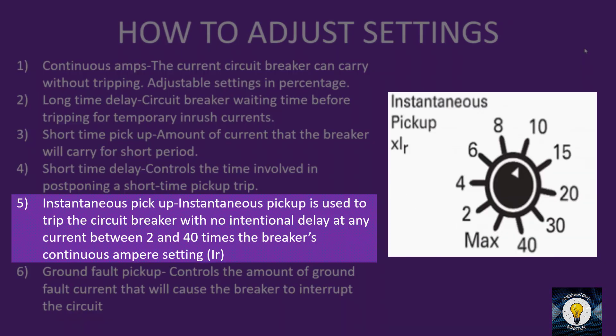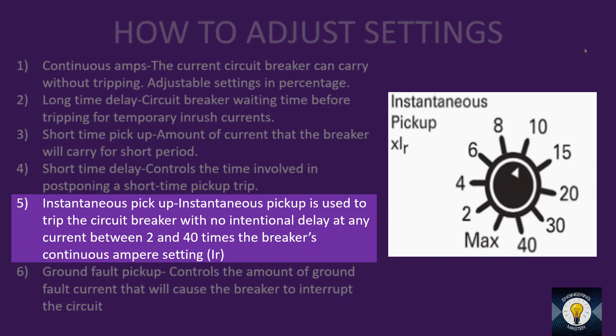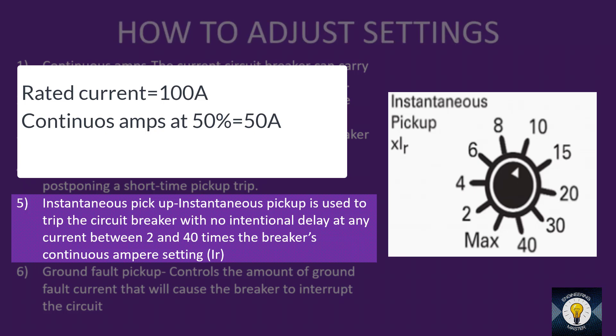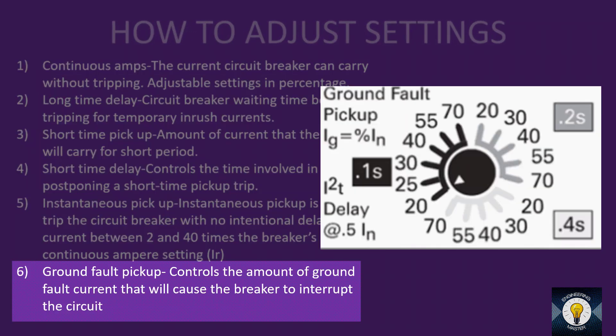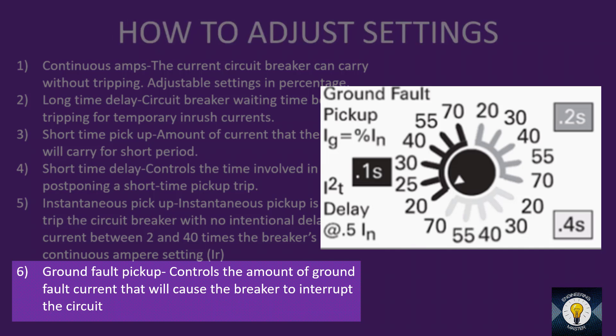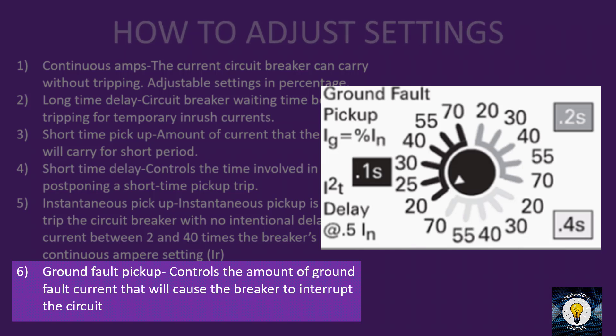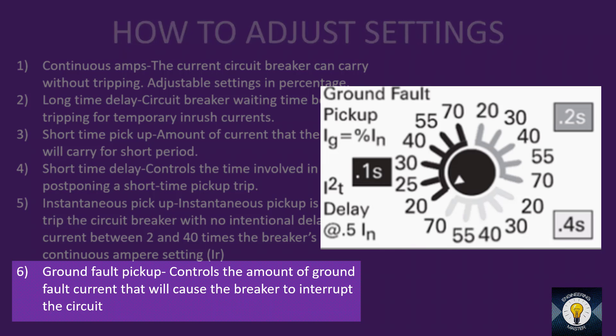Instantaneous pickup is used to trip the circuit breaker with no intentional delay at any current between 2 to 40 times the breaker's continuous amp setting. For example, if continuous amps is 50 A and the instantaneous pickup switch is set to 20, then above 1000 A the breaker will trip instantaneously without any time delay. Ground fault pickup is the amount of fault current that will cause the breaker to interrupt the circuit. The knob is available from 20% to 70% of the rated current IN. If the knob is at 20%, any ground fault current exceeding 20% of IN will trip the breaker instantaneously.